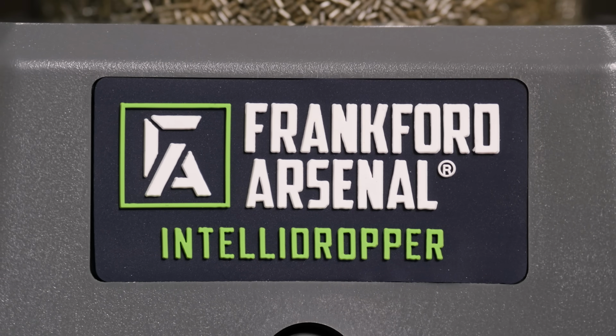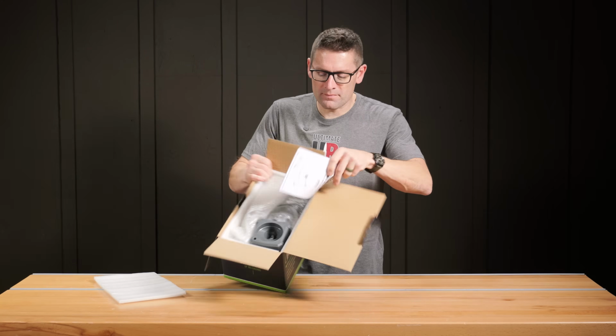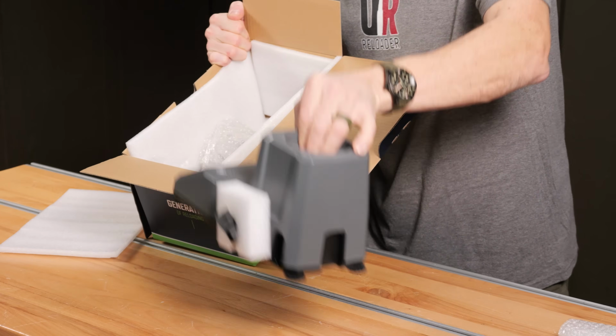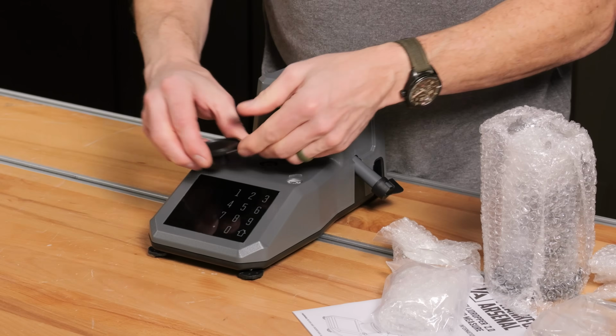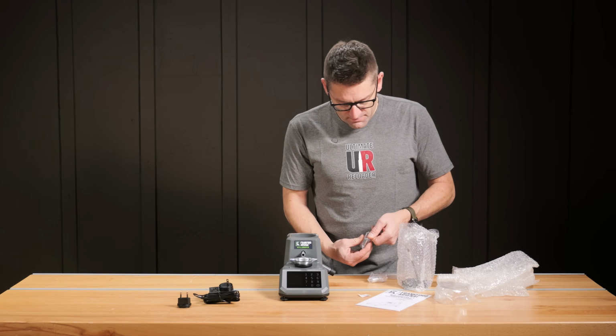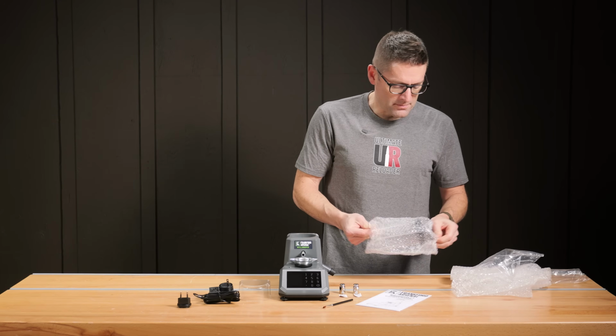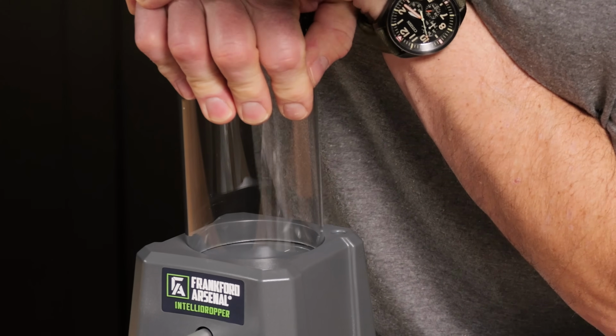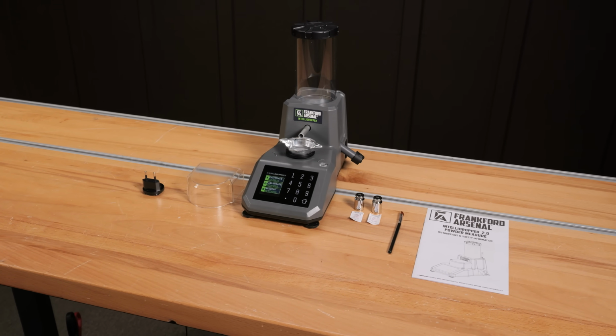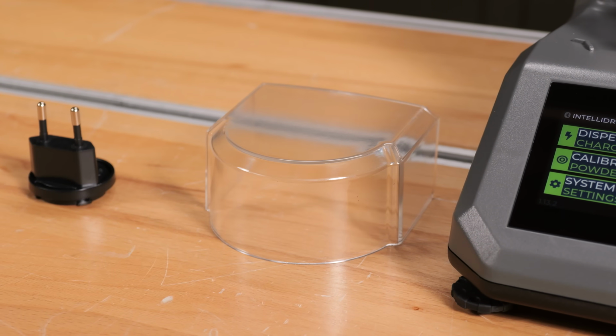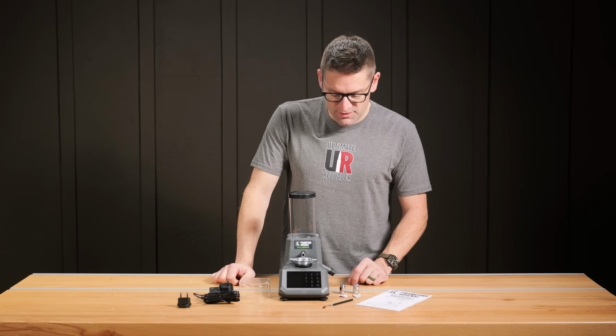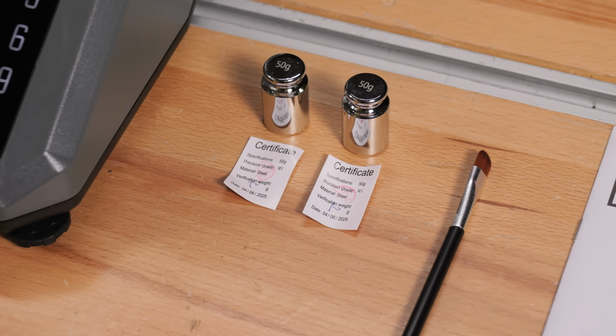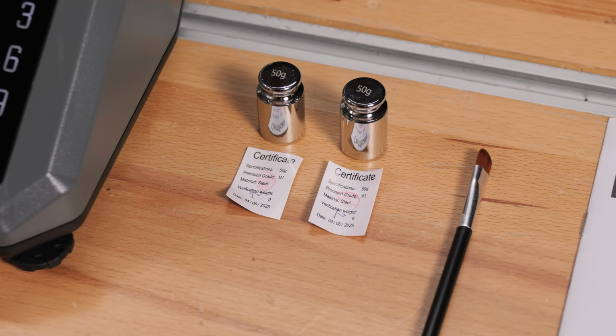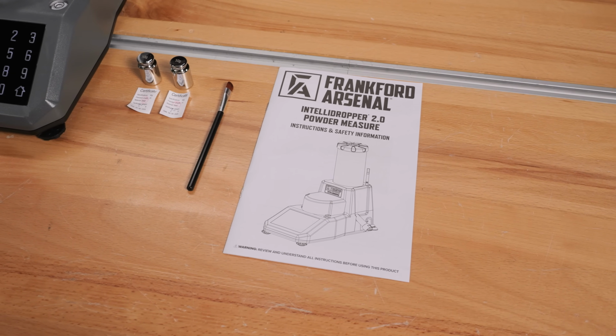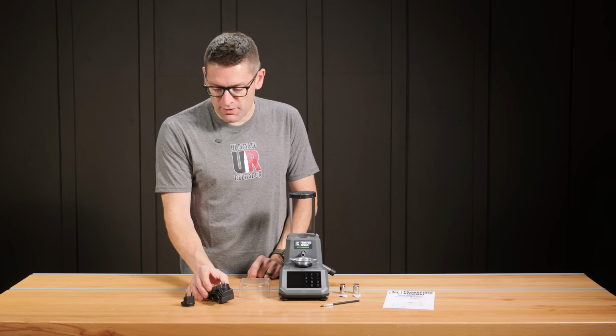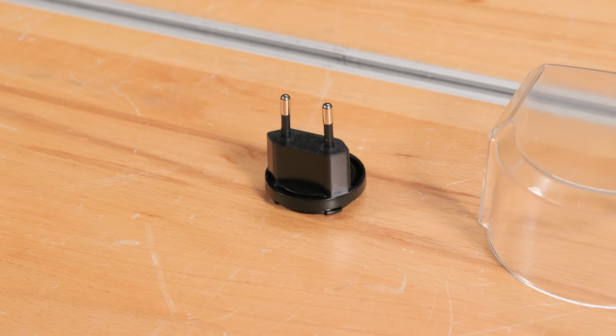I'm going to waste no time and get this Intellidropper 2.0 out of the box. So here's what was in the box. We've got, of course, the unit itself, the pan, the shield to avoid fluctuations due to air currents and whatnot, and to keep dust off of the pan. We've got two 50-gram weights with certificates, which is great. They've been validated for the purposes of calibration. The instruction manual, the powder brush, the power adapter configured for North America, and there's also another international plug option here as well. So that's the box contents.